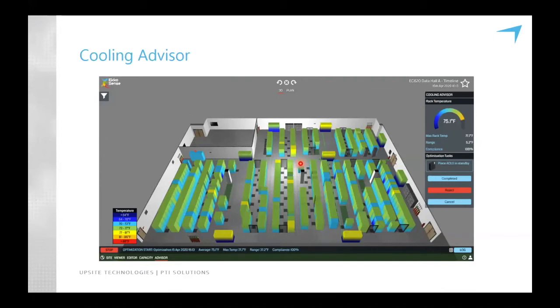This image shows what the cooling advisor looks like. And you see here on the left the rack temperatures and what maximum allowable intake temperature you would like the software to consider. And then a list of optimization tasks. You can see here with these green crossbars that this cooling unit is highlighted and tagged for being placed in standby, because the software has identified that the cooling units do not have variable speeds and that this cooling unit is not necessary. It can be turned off and then the fan energy from that cooling unit can be saved.